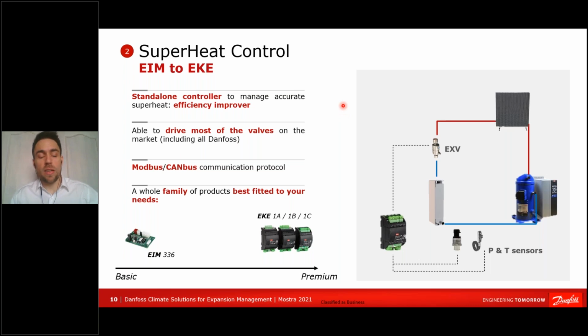After the valve, there is another device which is very important to do the expansion. You need to control the valve. You need to send it a signal, open or close. For that, you have a superheat control. The superheat controller is really designed so it can mimic what we had with the TXV. With the TXV, you don't need any sort of intelligence. It does the regulation itself. You just need the valve.